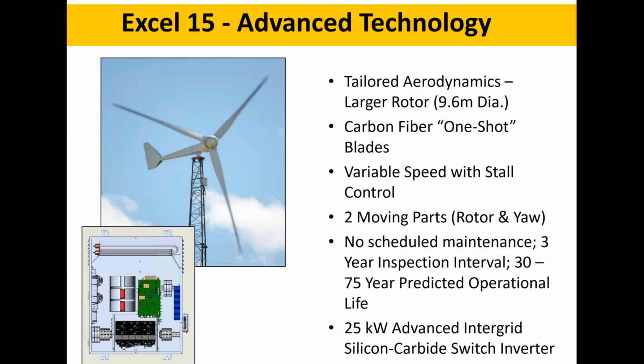The 15 kW, which took about 5 years to develop, has a 9.6 meter diameter with tailored aerodynamics. Even though it has a much bigger rotor, it can go on the same towers and foundations as the 10 kilowatt, with over double the energy output. It has carbon fiber single-shot blades, is variable speed with stall control, has only 2 moving parts, no scheduled maintenance, a 3-year inspection interval, and a 30 to 75 year predicted operational life. Since we have turbines that have been in operation for over 40 years, we have some basis for those projections. We've paired that with a custom-designed silicon carbide switch inverter, 25 kW in capacity, single phase.